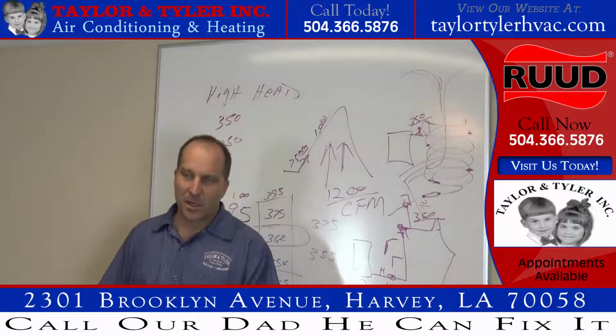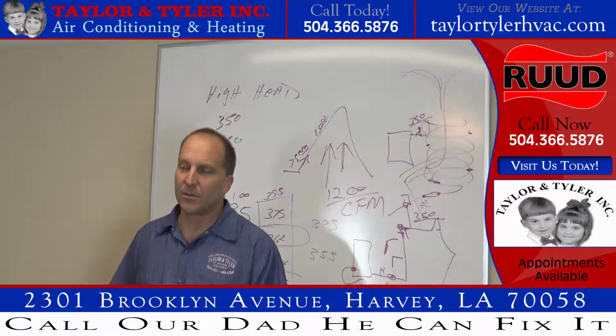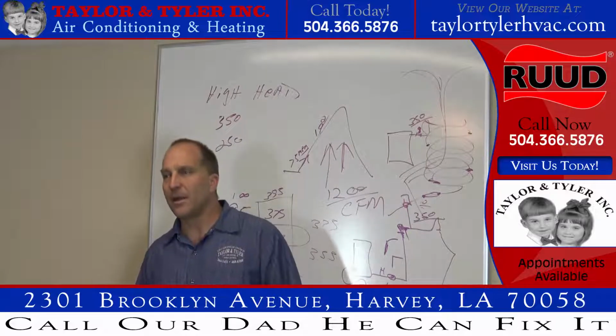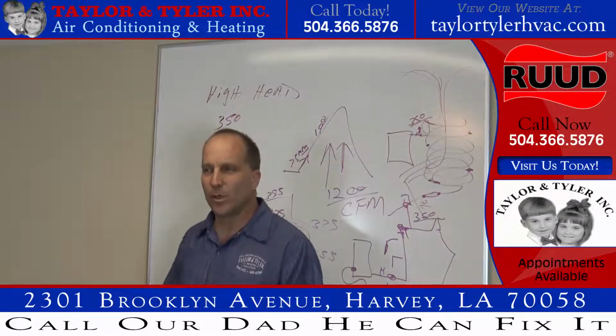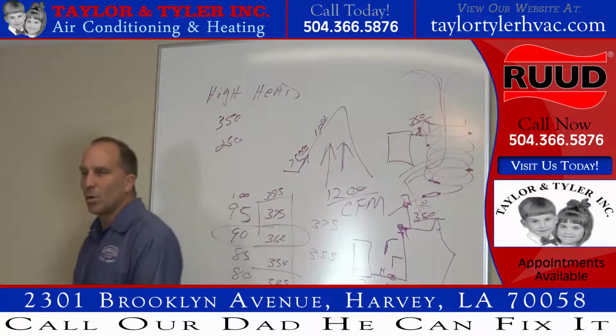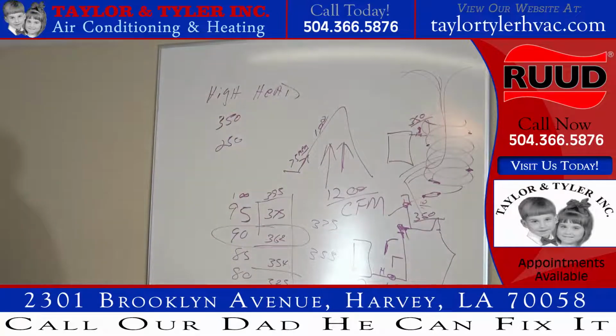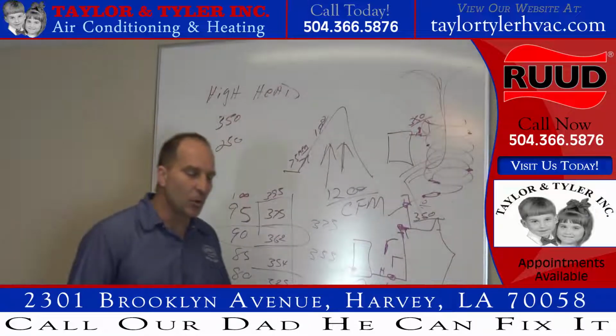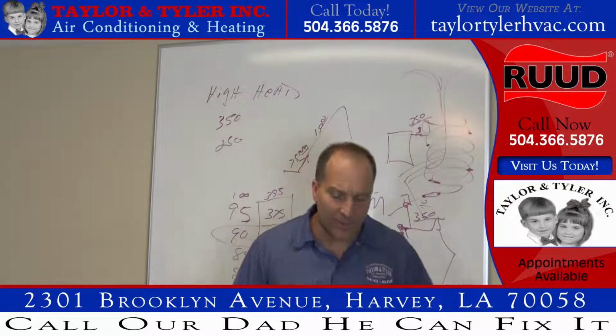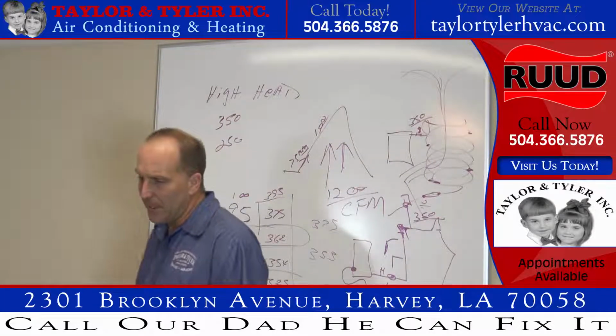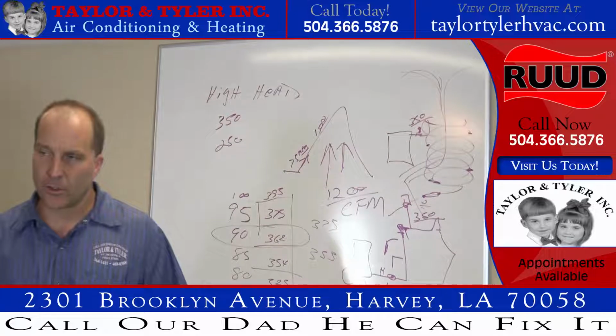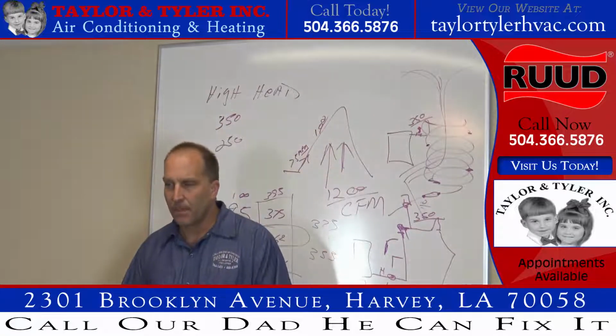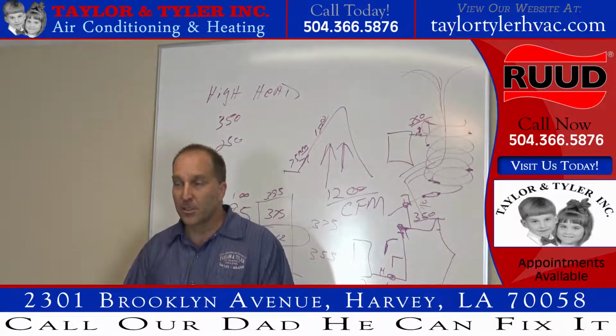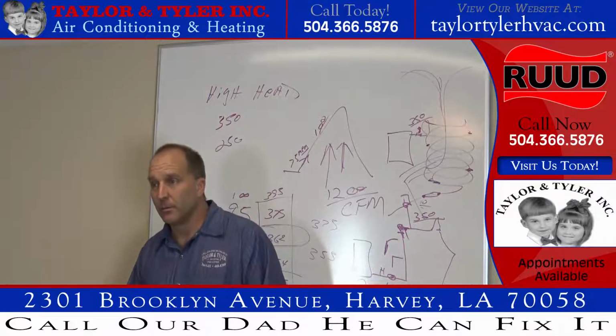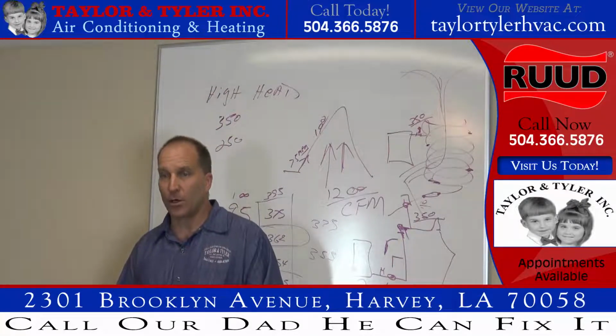So I'm going, man, well, my suction pressure is 100 pounds. I needed 118 is what I'm looking for, but my subcooling is 22. Well, if my subcooling is 22 and it's supposed to be 12, is my system overcharged or undercharged, guys? If my subcooling is 22 and it's supposed to be 12, and I've got an expansion valve system, is my system overcharged or undercharged? What is it supposed to be? It's supposed to be 12, but it's 22. Then it's overcharged, right?